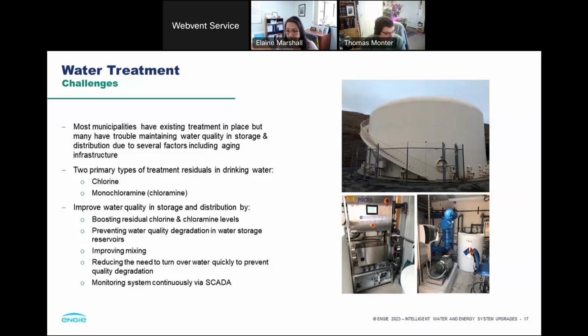What ENGIE proposed was to install new tank mixers and new automated treatment systems to maintain residual levels in the tanks. That would also allow them to store the water in the tanks for longer periods without water quality degradation, avoiding having to turn that water over. So it saves a lot of water from getting wasted, and also saves a lot of pumping power needed to maintain water quality in those tanks.